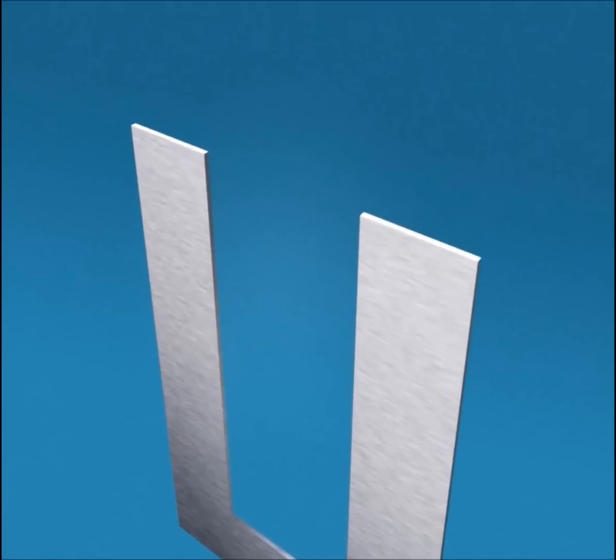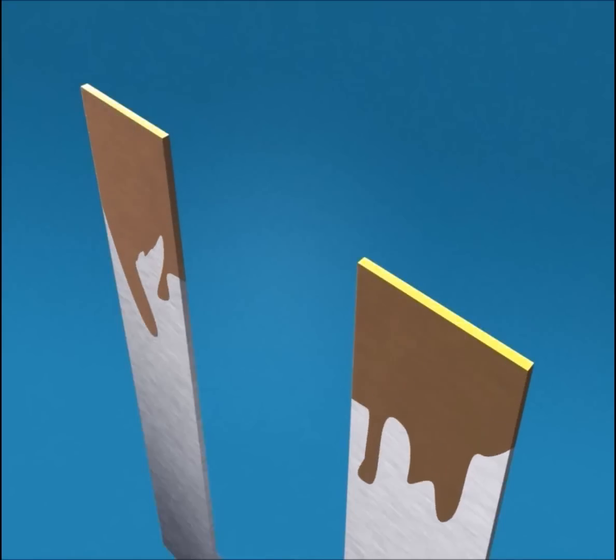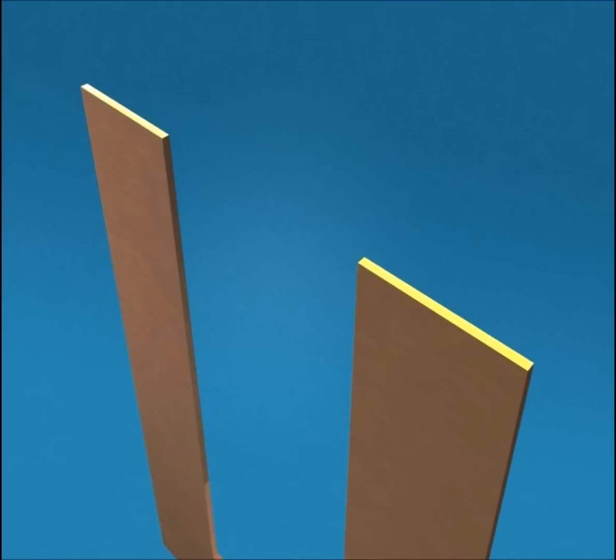The thickness of these laminations is varied between 0.25 mm to 0.5 mm. As steel is conductive, laminations are electrically insulated from each other via very thin coating of insulating varnish or by the use of an oxide layer on the surface.